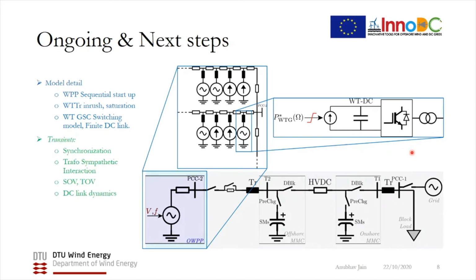The main transients of interest are synchronization and switching overvoltages during sequential startup of wind turbines inside the plant, transformer sympathetic interaction and transient overvoltages, along with DC link dynamics. Planned studies aim to ensure stability and robustness, for example during the farthest wind turbine disconnecting and reconnecting, or during faults in soft start energization.